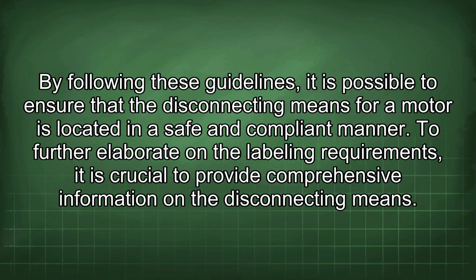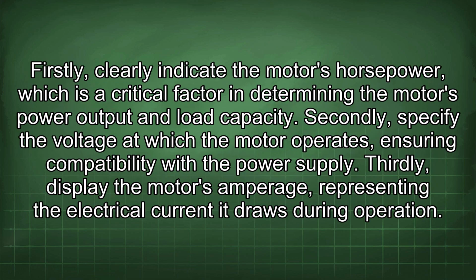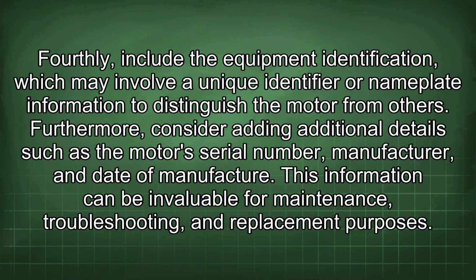To further elaborate on the labeling requirements, it is crucial to provide comprehensive information on the disconnecting means. Firstly, clearly indicate the motor's horsepower, which is a critical factor in determining the motor's power output and load capacity. Secondly, specify the voltage at which the motor operates, ensuring compatibility with the power supply. Thirdly, display the motor's amperage, representing the electrical current it draws during operation. Fourthly, include the equipment identification, which may involve a unique identifier or nameplate information to distinguish the motor from others.